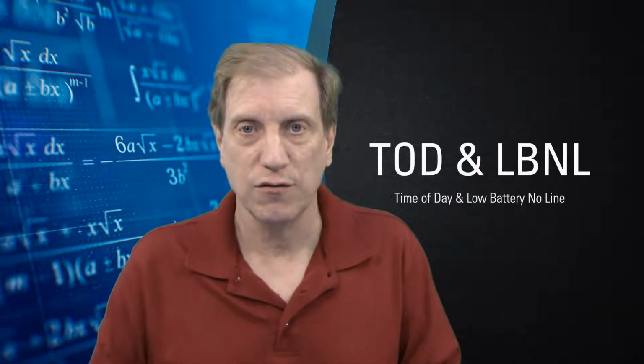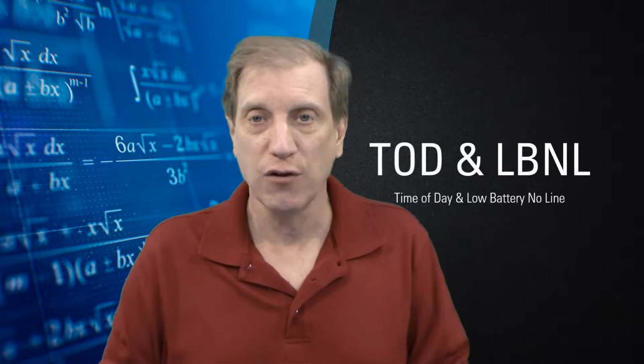So why would you want to use this one? Let's say you've got an intersection with high volume, maybe at the top of an exit ramp. If during rush hour you had an outage and you happened to be in flash, that could be bad because you could be backing traffic up onto the freeway, which can be an unsafe condition. Those are things you've got to decide as engineers as you lay out your signals. But if you wanted to, you could still have it go to flash at other low battery conditions.